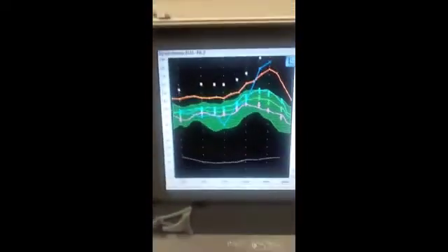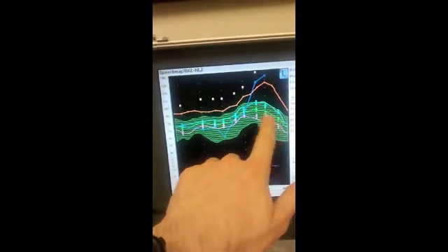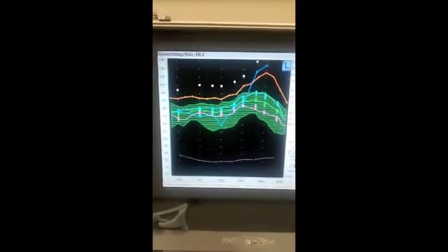Now, the reason you really couldn't hear the speech is the hearing aid's in this box and attached here. But as you see, I've made these gain adjustments, and the solid green line is hitting the green crosses, so I know the hearing aid is amplifying correctly.